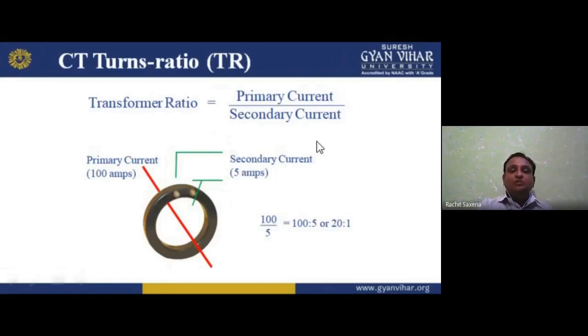So the transformation ratio is the ratio between the primary current of the CT and the secondary current of the CT. For example, if the primary current is 100 ampere and the secondary current is 5 ampere, the ratio will be 100 by 5, that is 20 to 1. That is the CT ratio, or we can say the CT turn ratio: primary current to secondary current. The primary current always has the higher value and the secondary current the lower value, because it is a step-up construction, but as per the current, we can say it is a step-down construction. In step-up construction, voltage is higher and current is lower. In step-down construction, voltage is lower but current is higher. So I hope you understand this turn ratio.